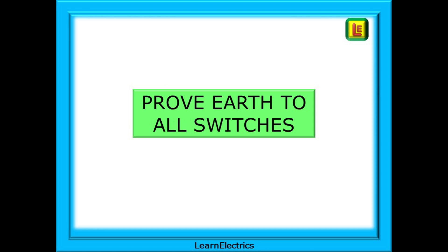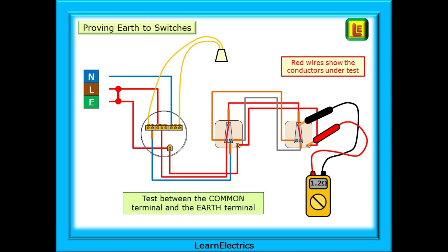We should prove that the earth or CPC conductor is continuous through the circuit to both switches. We may not need the earth today but it may be required in the future, so we need to check. Move to the furthest switch and low ohms test between the earth terminal and the common terminal of the switch. A low ohms reading should be returned showing that the CPC is continuous back to the consumer unit.